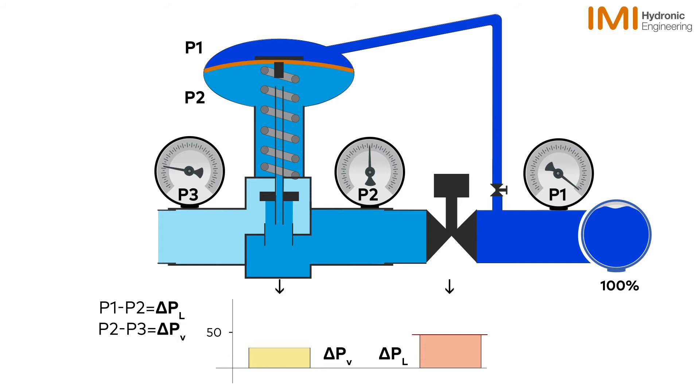As flow decreases in the circuit, initially delta PV will decrease and delta PL will increase as their pressure increases on the control valves.